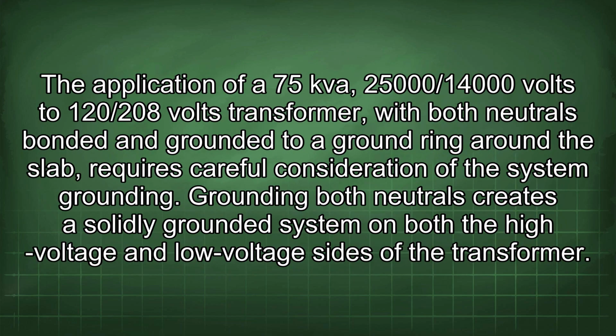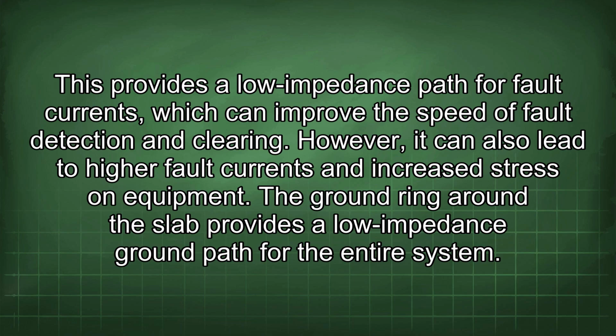The application of a 75 kVA, 25,000/14,000 volts to 120/208 volts transformer with both neutrals bonded and grounded to a ground ring around the slab requires careful consideration of the system grounding. Grounding both neutrals creates a solidly grounded system on both the high voltage and low voltage sides of the transformer. This provides a low impedance path for fault currents, which can improve the speed of fault detection and clearing. However, it can also lead to higher fault currents and increased stress on equipment.